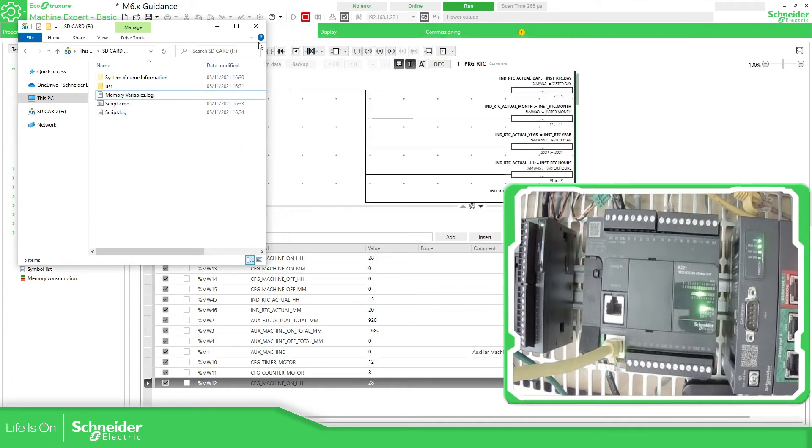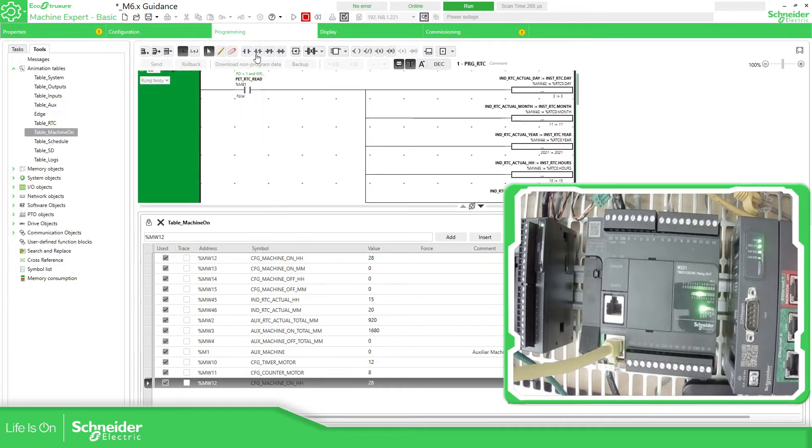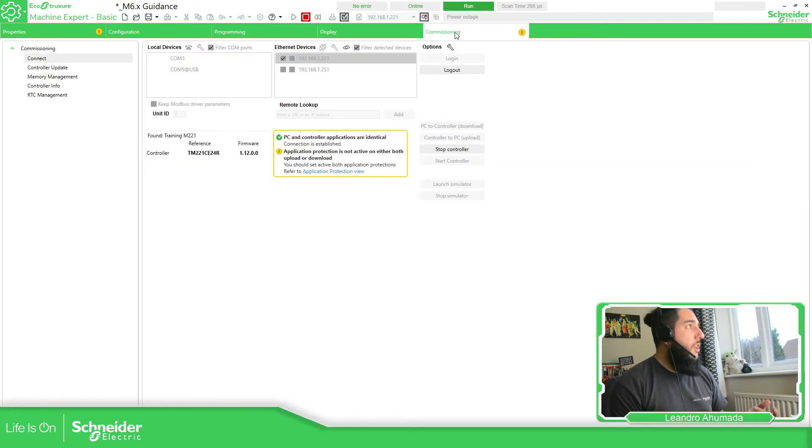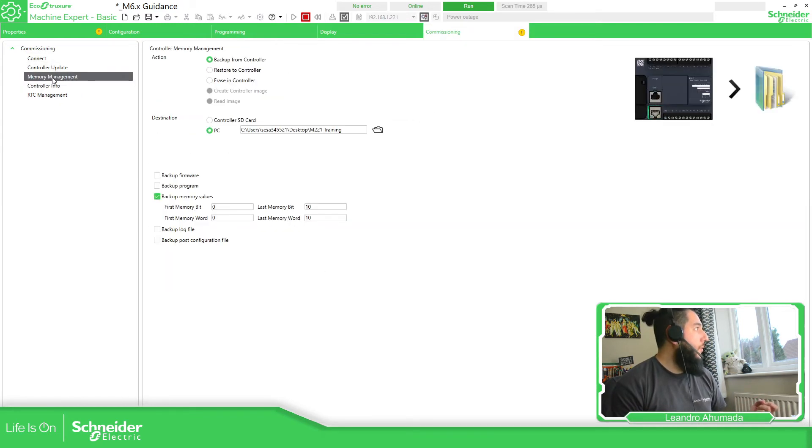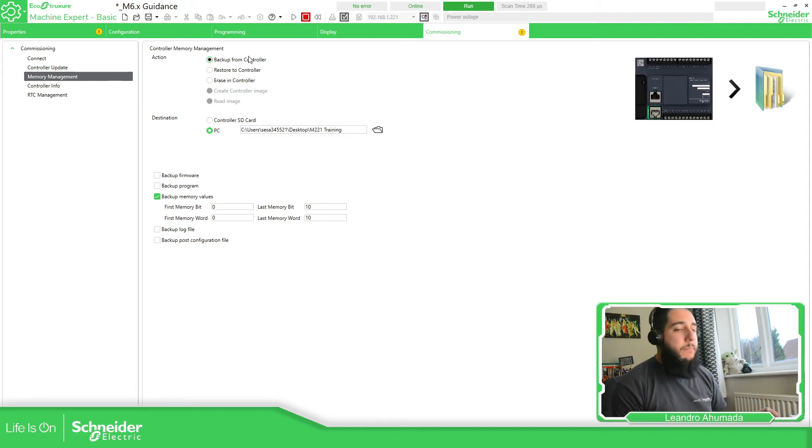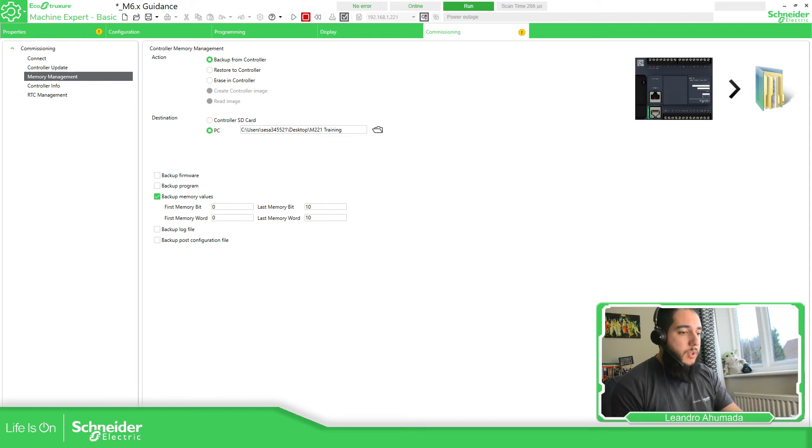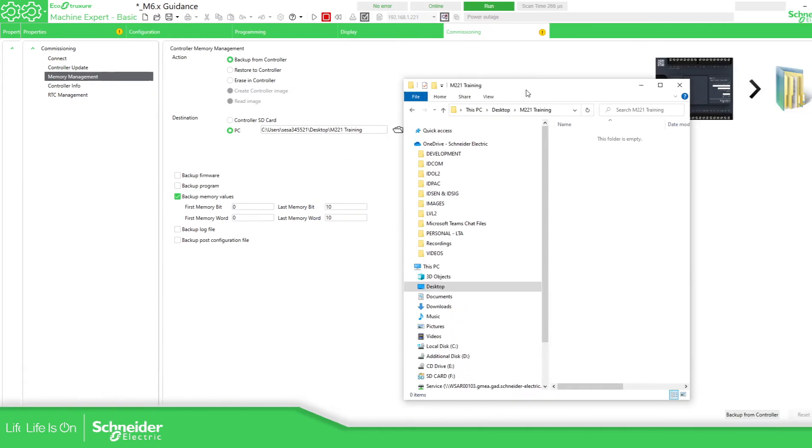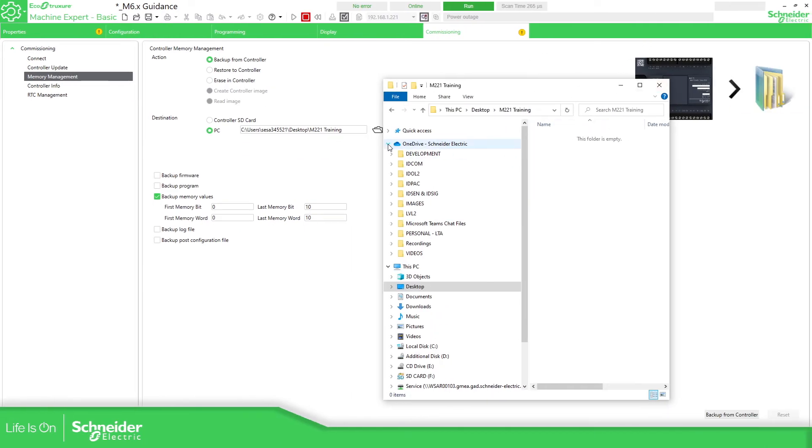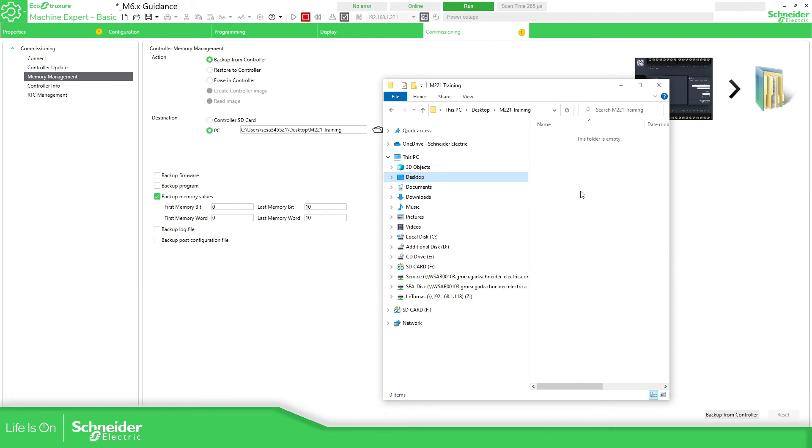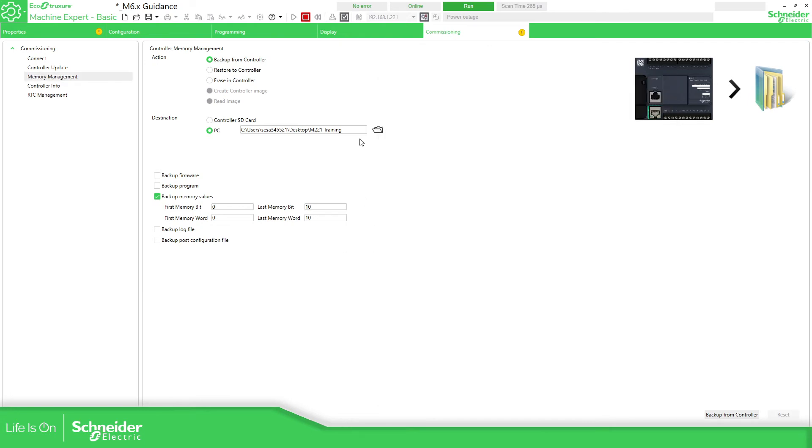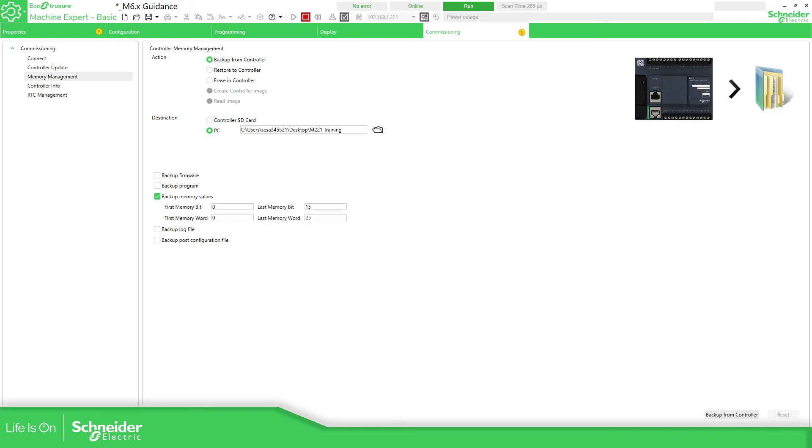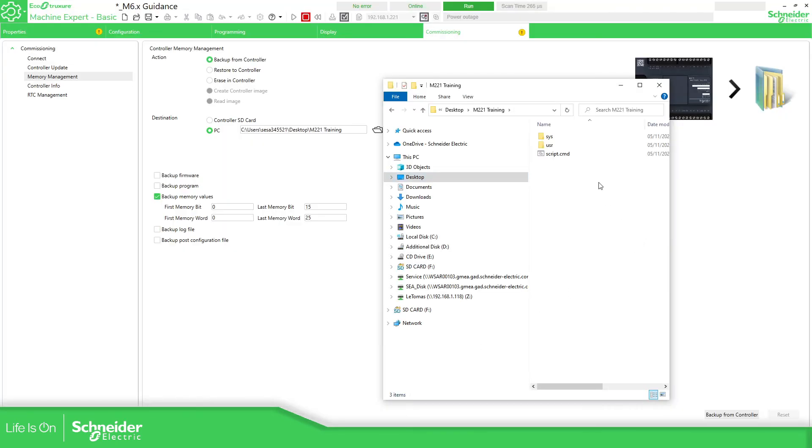Another way to do this instead of using the SD card, we can go to the commissioning, and while we are connected to the controller we can go to the memory management to make a backup of the actual PLC. This is the folder that I'm working with, M221. We can specify the addresses that we want to take a look. Let's say this and this, backup from the controller right now while we are connected, backup. Now we open this again, we have this configuration.